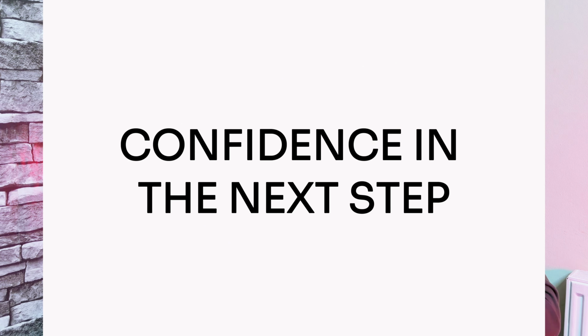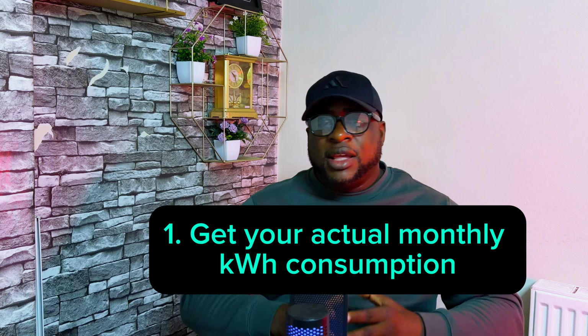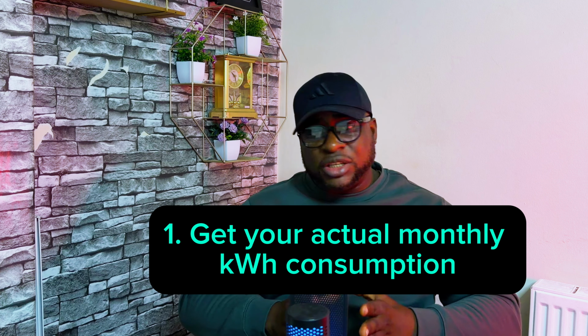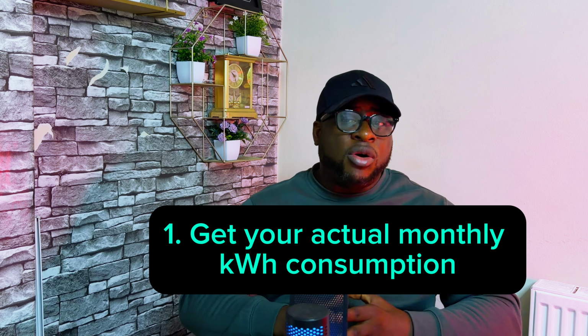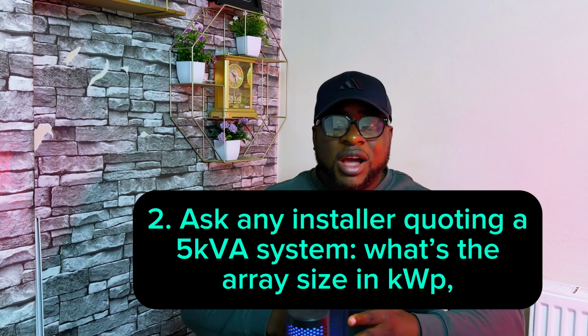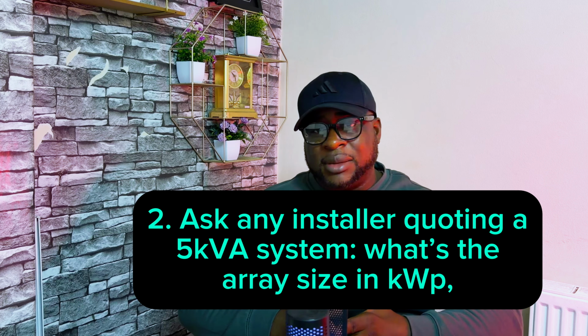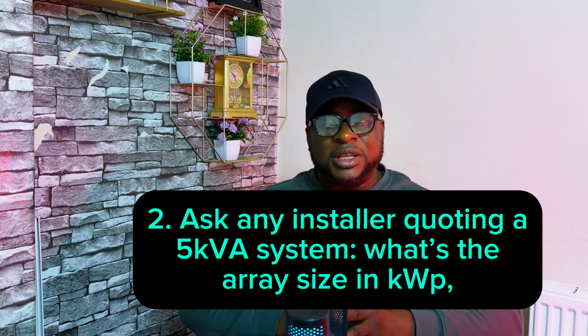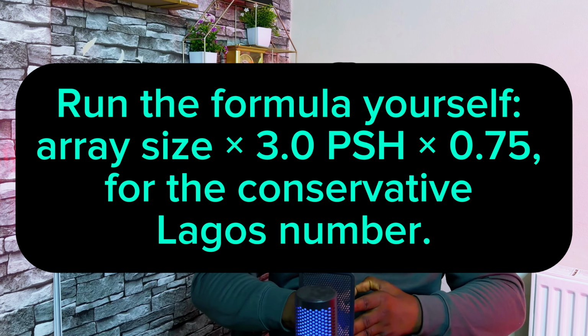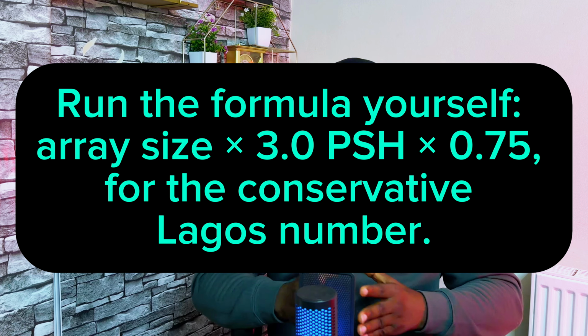So here is what to do with this information practically. One, get your actual monthly unit consumption in kilowatt hours from your electricity bill or your generator fuel log. Two, ask any installer quoting a 5 kVA system what the array size in kilowatt peak is, and what the expected rainy season daily output is, not just the annual average. Three, run the formula yourself. That is the array size multiplied by 3.0 PSH multiplied by 0.75 performance ratio for the conservative Lagos number. If their quote cannot survive that math, ask why.